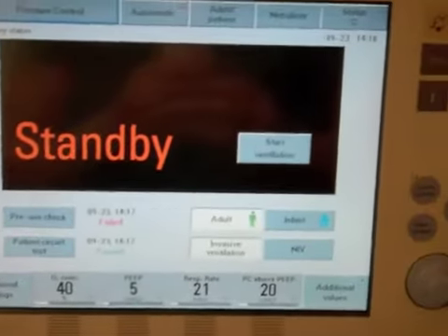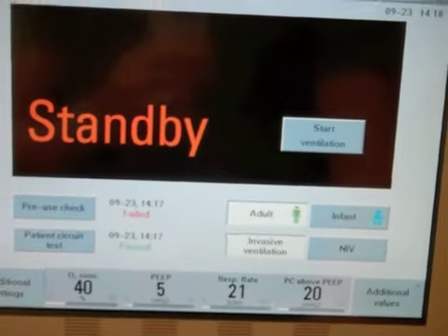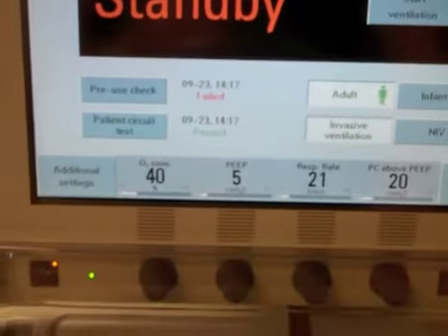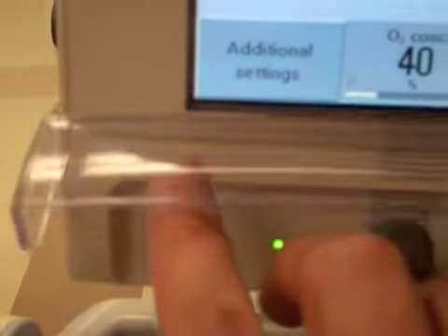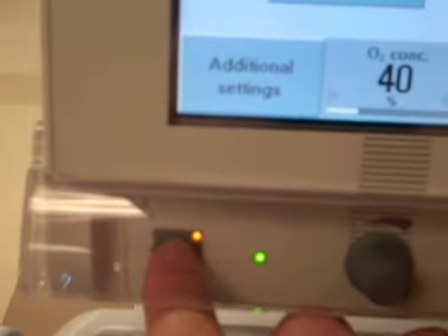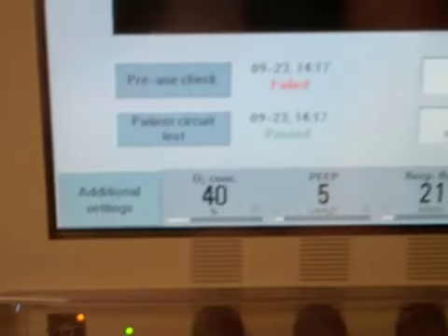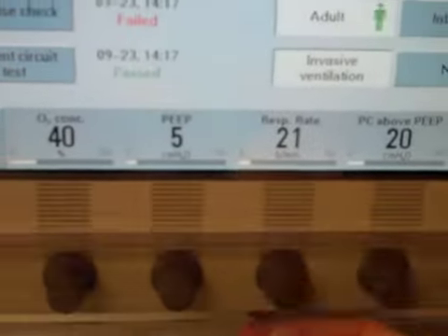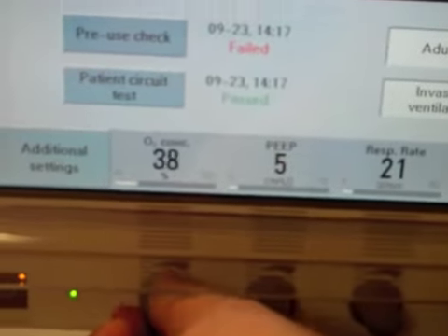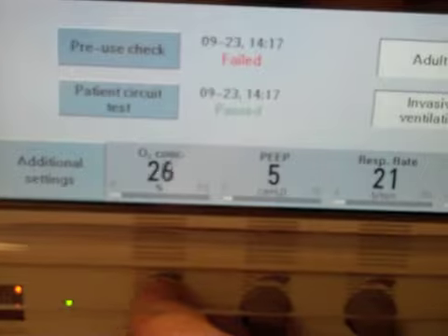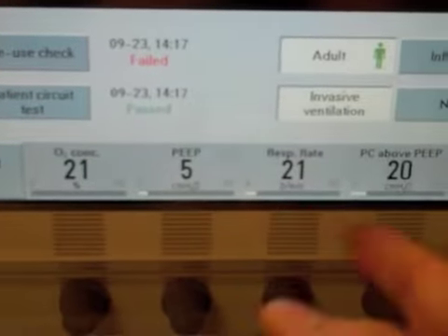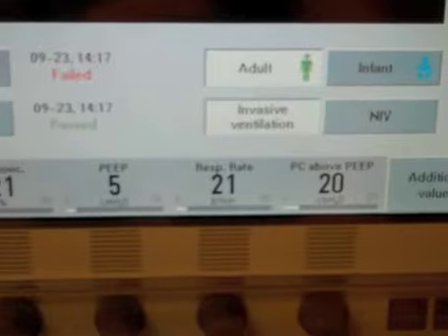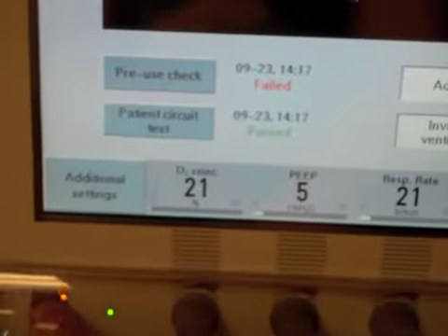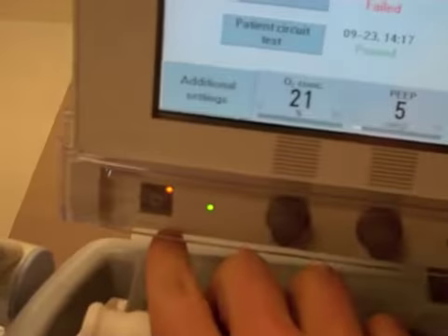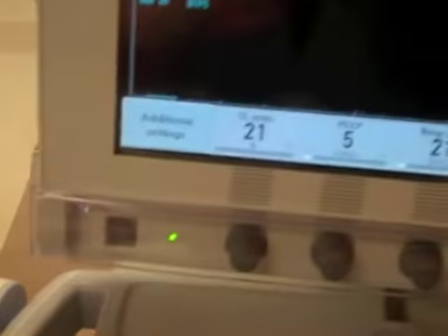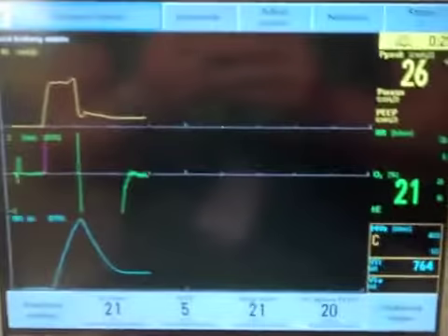Notice it's not ventilating yet. I'm not spewing out any kind of gas into the room, and what you actually have to do to get this machine to ventilate is down in the bottom here, you have to lift up this window and press the on standby button or start standby button. And you'll notice also down here you've got some control. Let's say I didn't want 40% oxygen. Without going back into your mode or parameters, you can choose which FiO2, PEEP, respiratory rate, and your distending pressure that you want.